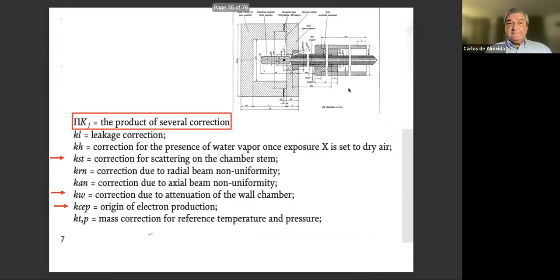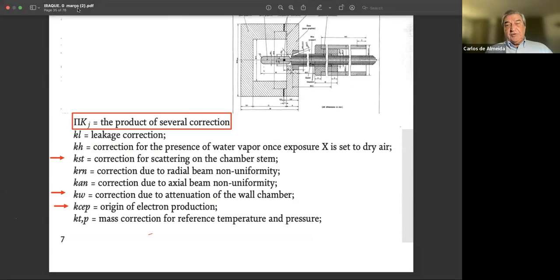Next slide also shows that several of the parameters have to be taken care of. And the main ones are the correction for the scattering in the chamber stem, in this area of the chamber. Then the correction due to the attenuation of the wall, because as you introduce the wall, and you remember that the wall has several functions. One is to generate electrons that will create ionization in the chamber. So in this process, you have some attenuation. You have also the question of where in this wall is the point that should be considered the point of production, where the electrons originate that are going to produce the ionization inside of the chamber.